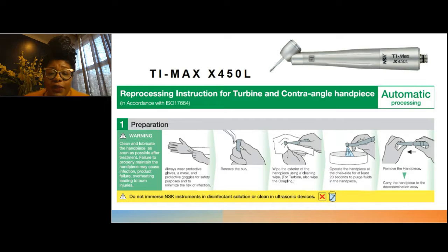Removing the bur, wiping down the exterior of the handpiece. It's also telling you to flush it for 20 to 30 seconds, removing the handpiece from the coupler. All of these things are being communicated to you as steps that need to be taken in the operatory before it actually goes to get additional reprocessing.